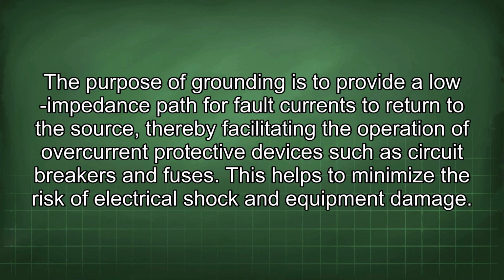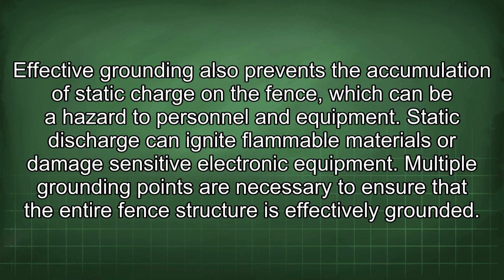The purpose of grounding is to provide a low impedance path for fault currents to return to the source, thereby facilitating the operation of overcurrent protective devices such as circuit breakers and fuses. This helps to minimize the risk of electrical shock and equipment damage. Effective grounding also prevents the accumulation of static charge on the fence, which can be a hazard to personnel and equipment. Static discharge can ignite flammable materials or damage sensitive electronic equipment.